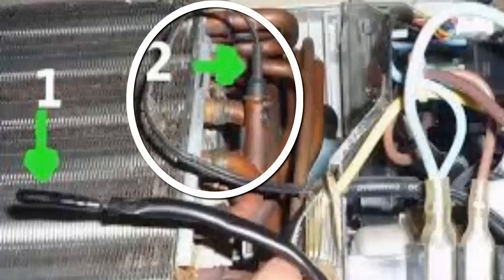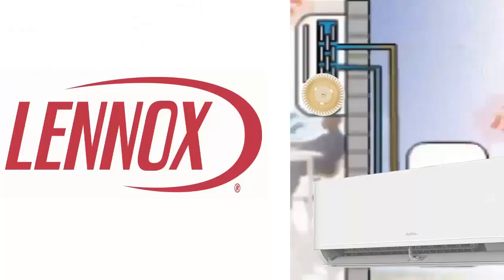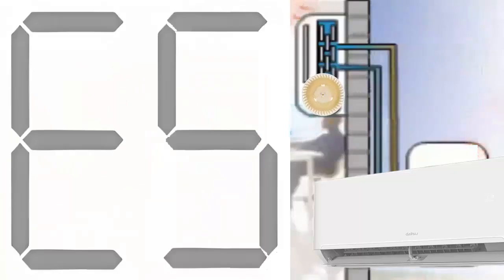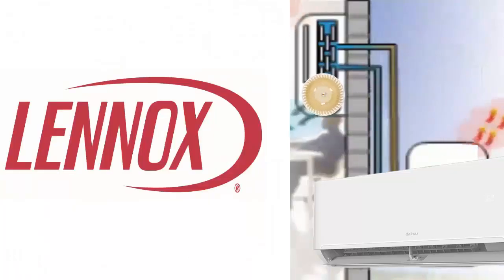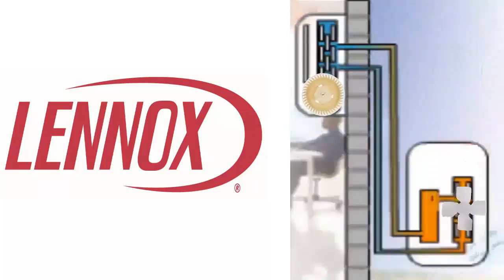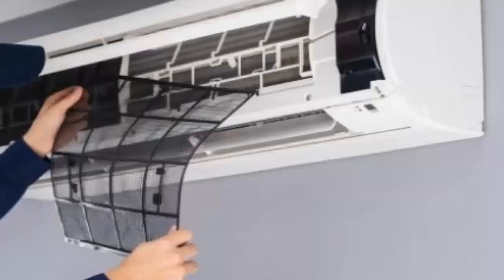Code F2 indicates a problem with the indoor unit coil temperature sensor, which is responsible for measuring the temperature of the refrigerant gas in this area to prevent coil freezing. Some LENNOX models may also display code E5 in this condition. It is important to mention that in some models, when coil freezing occurs in the indoor unit, besides checking the evaporator sensor, always remember to check the correct rotation of the indoor unit fan and the cleanliness of the air filters to ensure good airflow in this area.